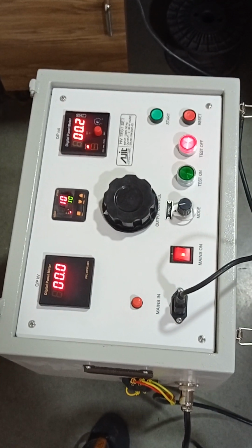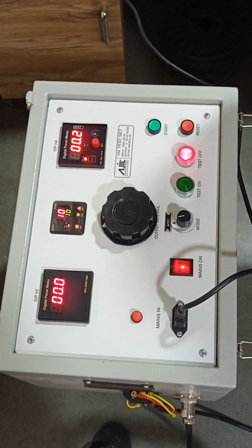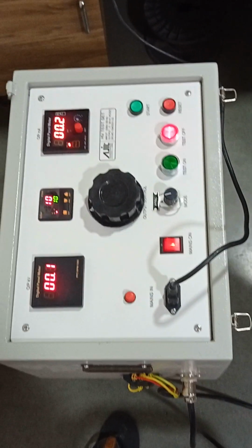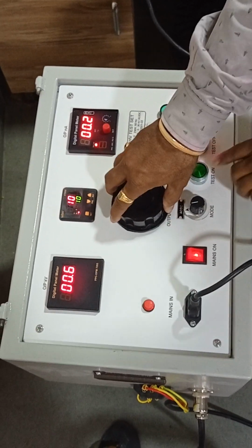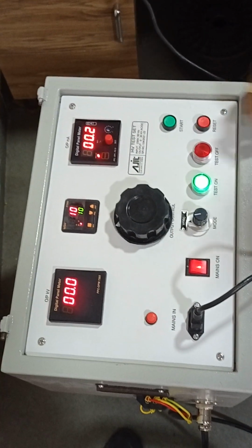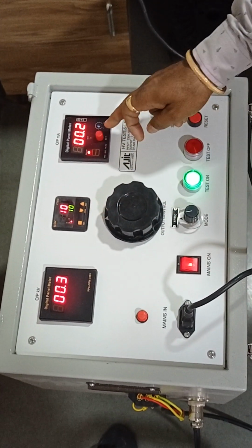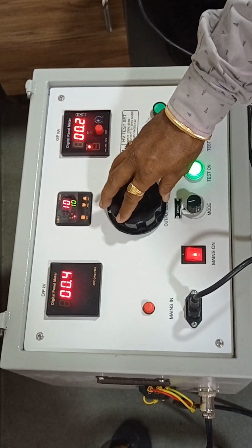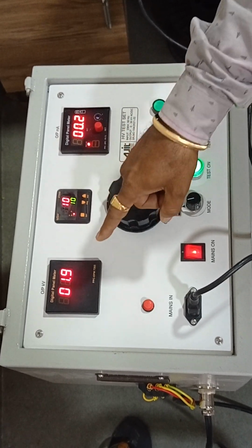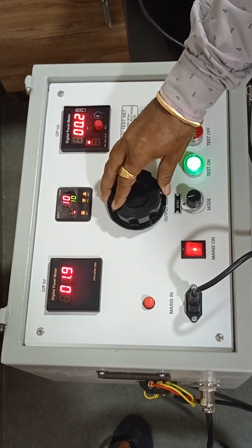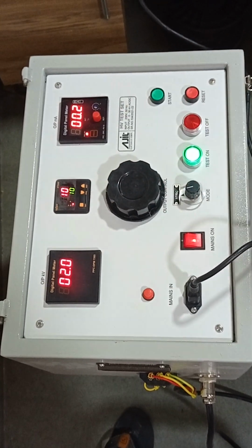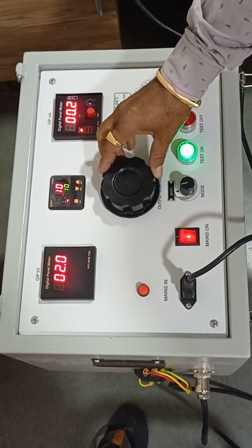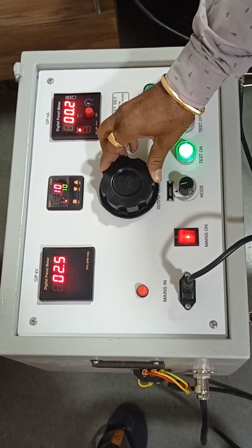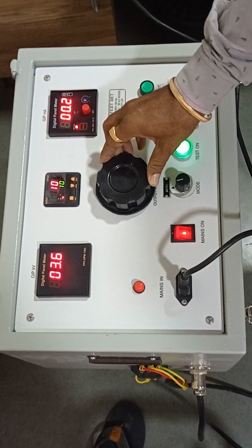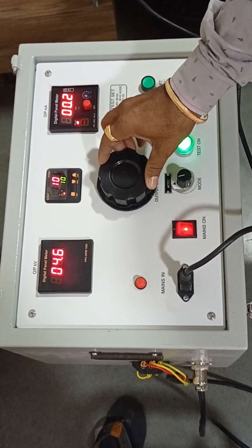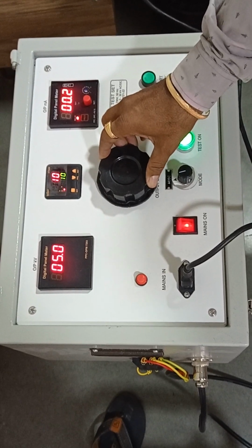Now we will see the high voltage. We have removed the shorting link between the high voltage and ground, and in this case if we operate the instrument, there will not be any current flowing directly through the ground because the output terminal is open. The value on the kV meter is the high voltage output at the tip of the high voltage transformer. So gradually we can increase the voltage to any value for testing, and we can test it.